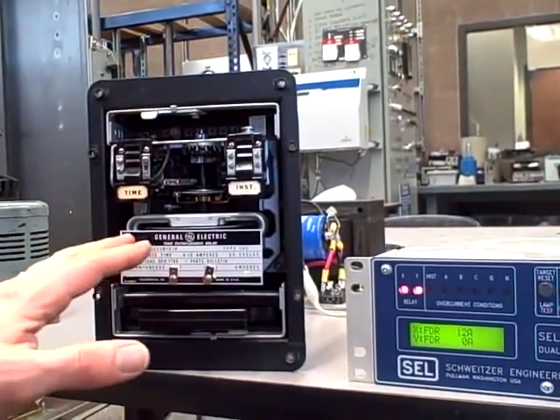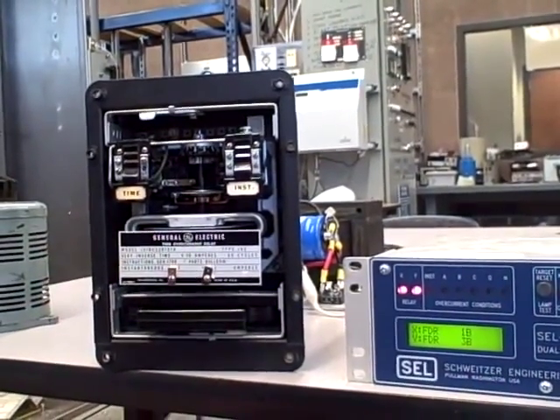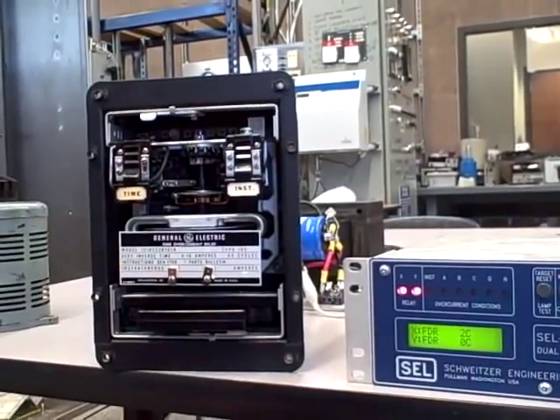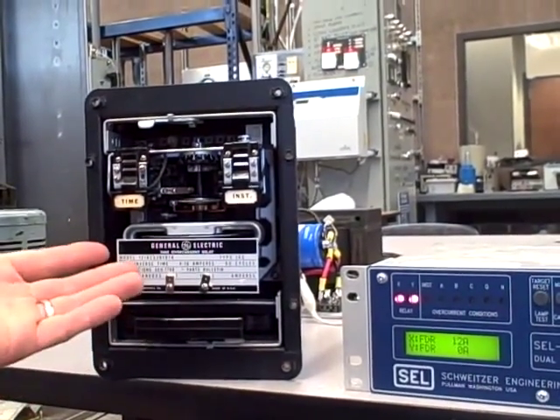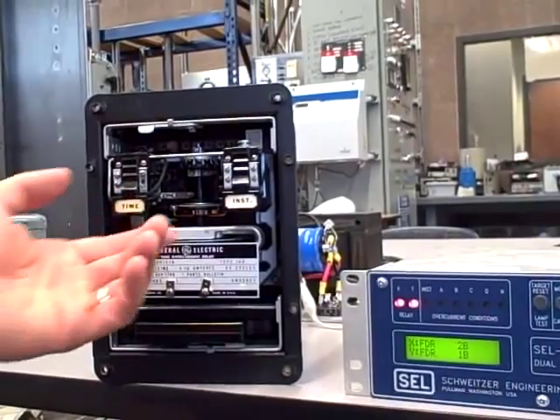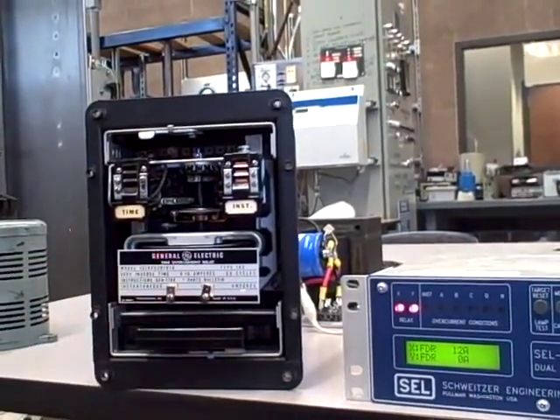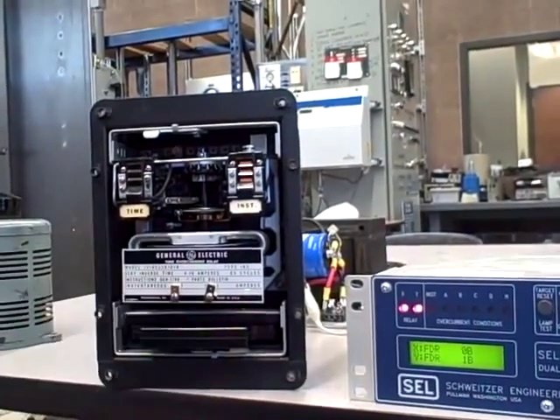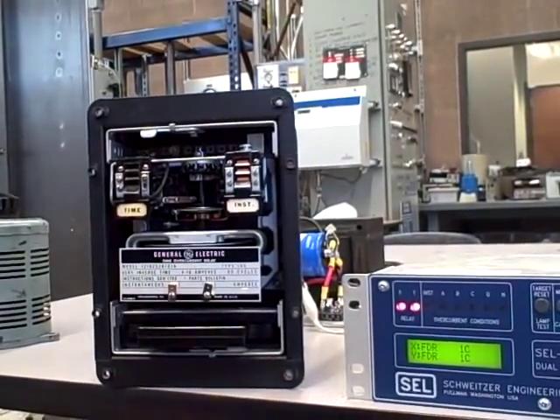So the time overcurrent function is a very basic protective function in power systems. We also have the instantaneous overcurrent function. If we exceeded a certain current value, a certain threshold there, it would trip the instantaneous. The target would appear, showing us we had an instantaneous trip, and that would immediately shut down the breaker with no time delay at all.